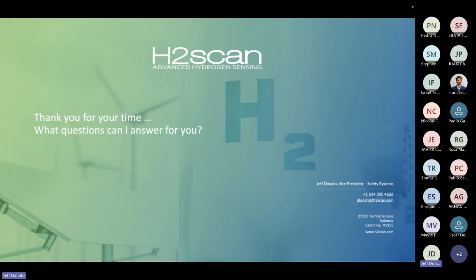Are you talking mainly of lithium batteries in your application? Yeah, of course. Okay, lithium-ion. So what we've seen in the industry is the code and the standards basically say, of course, we have to prevent accumulation. But in lithium batteries, we've seen OEMs who integrate the containers are also looking at early detection, not just accumulation. So say, for instance, in a lead acid battery, we consider a sensor that can operate in 5 minutes or less to be acceptable, because we're detecting slow rise accumulation. In a lithium battery system, obviously it's very quick, and so what we're seeing in the market is anywhere under 30 seconds. Most of the time it's between 5 and 15 seconds, because they're trying to use it for early detection.